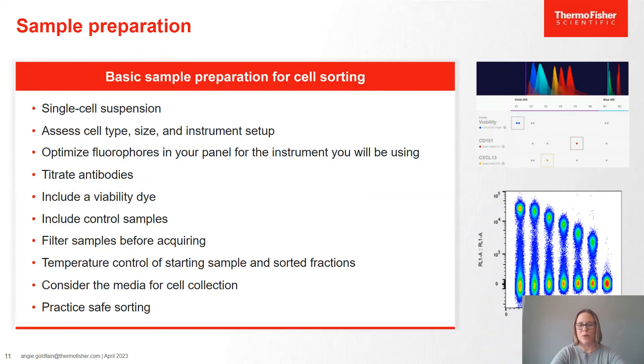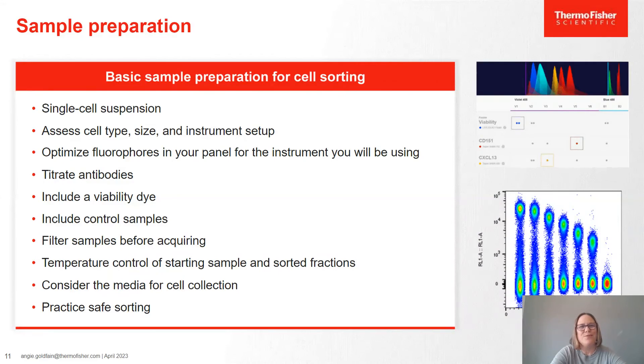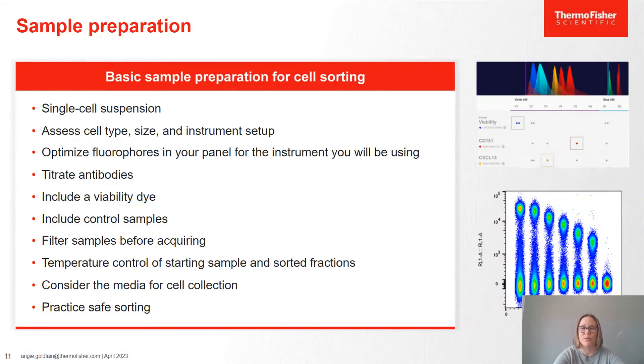Always include controls — for any experiment, you need controls. This can include single color controls to ensure your staining and prep went properly, negative controls to look at background autofluorescence, and fluorescence minus one controls if you have concerns about overlapping populations. All of these are critical to ensuring the quality of your experiment. Also consider temperature control — keep the cells happy through the sorting process. Many instruments have temperature control on both the sample input and sort output sides. Keeping cells at a steady temperature throughout sorting will really help with overall viability and recovery.